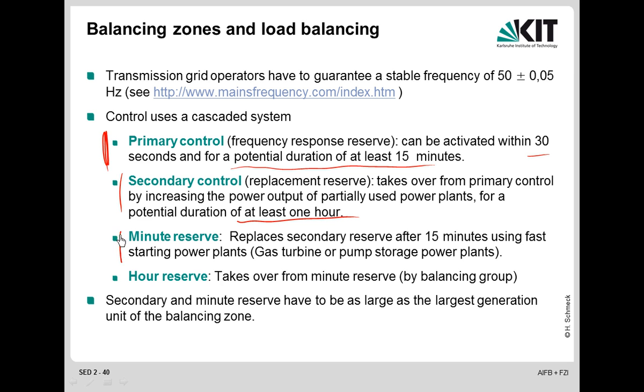And then we have the minute reserve, and this is triggered by a phone call of the transmission system operator, noticing that secondary control is not sufficient, there's a longer lasting deviation, and then minute reserve has to come in and take over. So this is gas turbine or pump storage power plants. And finally we have the hour reserve. This takes over from minute reserve. For example, if somewhere the power plant has failed, then it has to be replaced by another power plant which has to be started and so on. And this is actually managed then by the balancing group locally. This is not the task of the transmission system operator.